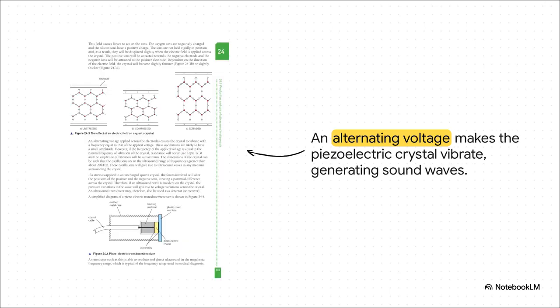Now this is where it gets really clever. If you apply a voltage across this crystal, its molecules try to line up with the electric field, and that forces the whole crystal to physically change shape. It either gets squeezed or stretched. So what happens if you apply an alternating voltage, flipping it back and forth super fast? The crystal starts to vibrate, compressing and expanding millions of times a second. And that vibration? Well, that's what creates the high-frequency ultrasound wave.